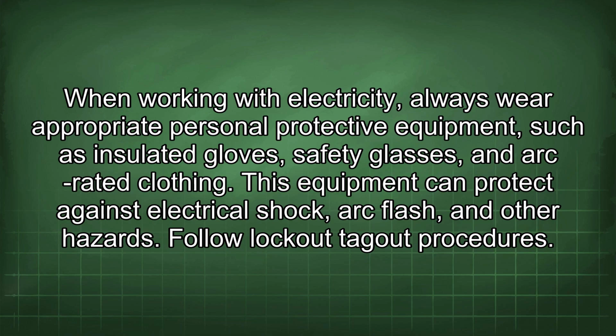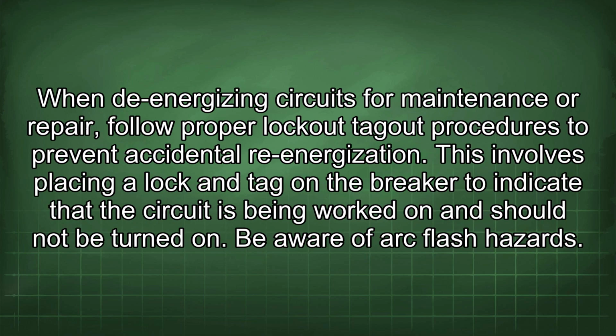Follow lockout-tagout procedures. When de-energizing circuits for maintenance or repair, follow proper lockout-tagout procedures to prevent accidental re-energization. This involves placing a lock and tag on the breaker to indicate that the circuit is being worked on and should not be turned on.